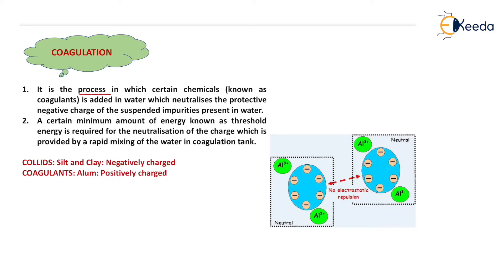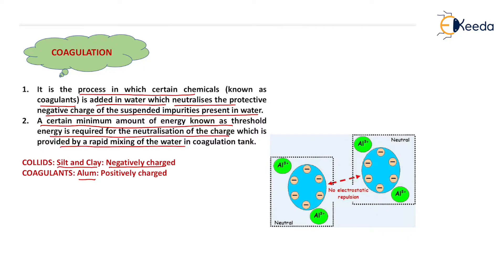Coagulation is the process in which certain chemicals known as coagulants are added in water, which neutralize the protective negative charge of the suspended impurity present in water. The impurities will be of silt and clay and they will generally be negatively charged. When we add coagulant in the form of alum, the alum will be positively charged. When positive and negative react with each other, charge neutralization takes place. A certain minimum amount of energy known as threshold energy is required for neutralization of the charge, which is provided by rapid mixing of the water in coagulation.